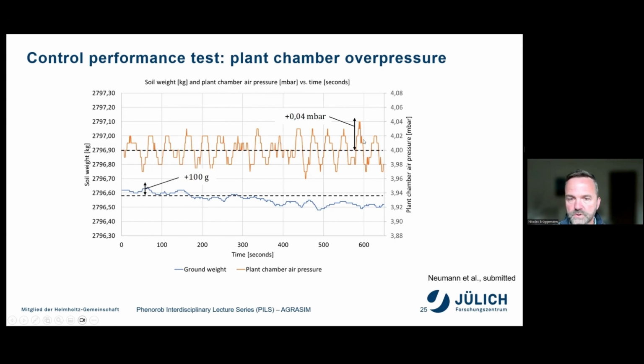But we managed, with a high precision control system of a high precision differential pressure transducer and high precision regulation, to maintain this pressure with that precision, so that we can maintain the weighing precision with a maximum deviation of 100 gram. Without this plant chamber on top, the precision would be even 1 order of magnitude better, plus minus 10 gram. But we decided to go for that overpressure approach to have always the security that no ambient air intrudes into the plant chamber, but whenever there's a leak, that air exits the plant chamber and it does not mix with ambient air.